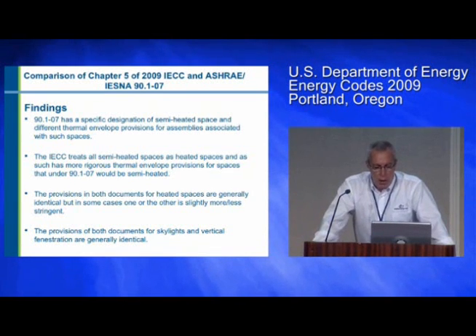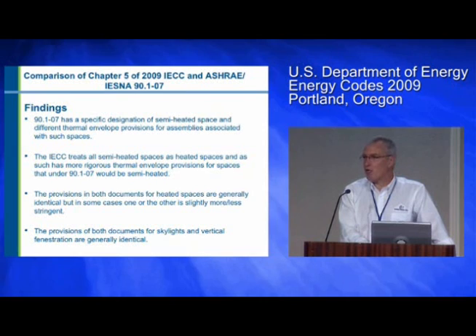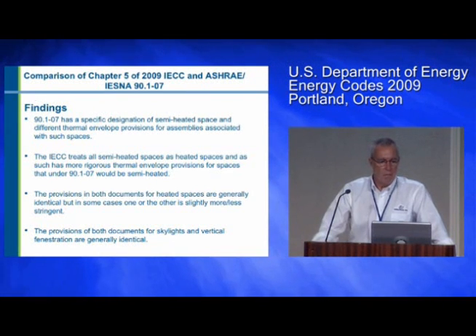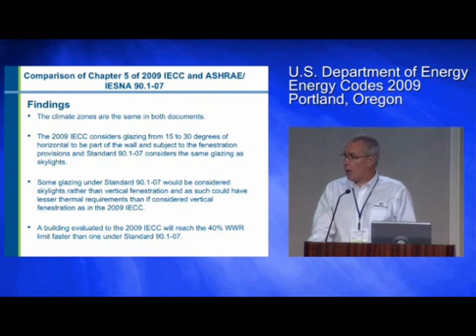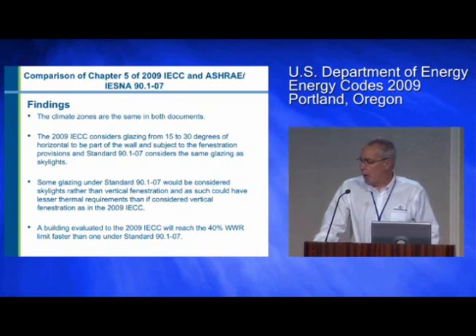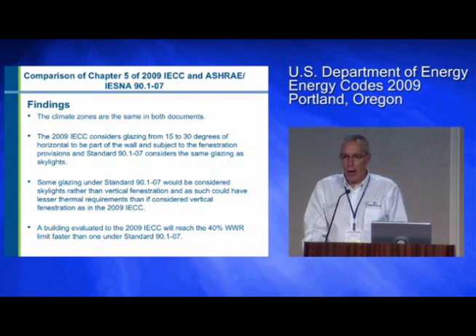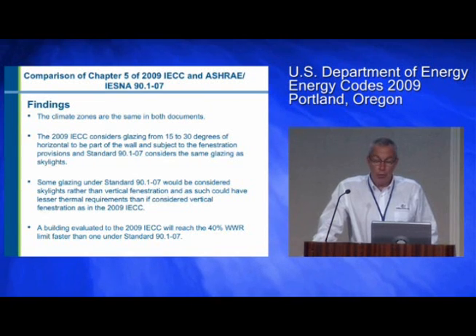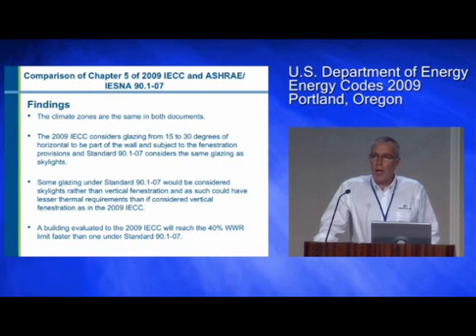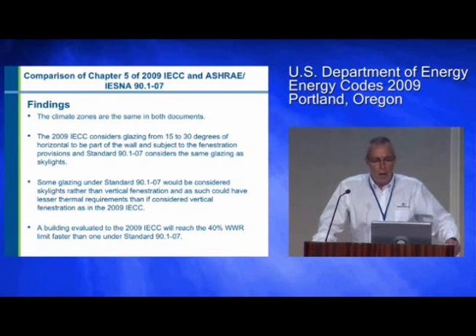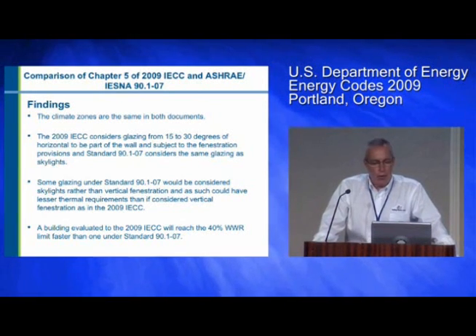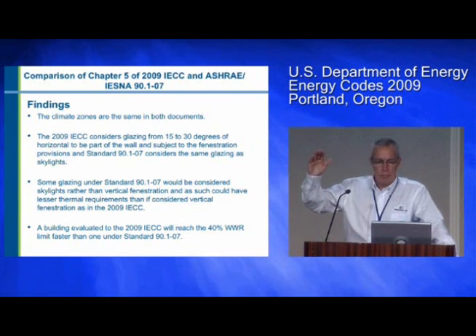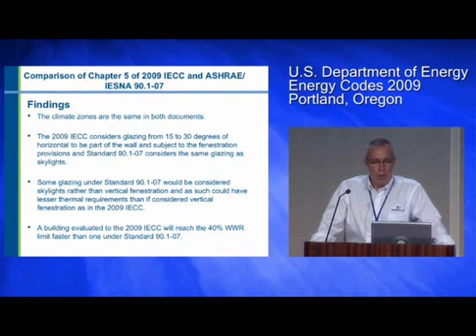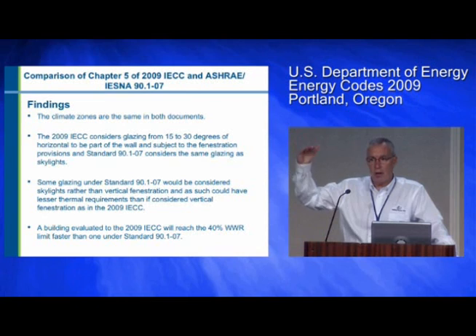But the provisions in both documents for skylights and vertical fenestration are also generally identical. The climate zones are the same in both documents. That's nice to know, that ASHRAE and ICC agree on how many heating degree days we should have in Fairfax County. But what's really interesting when you get into the glazing is the IECC says if your glazing is from 15 to 30 degrees of horizontal, it's part of the wall and subject to the fenestration provisions, but 90.1 considers that same glass a skylight, and you have skylight provisions.